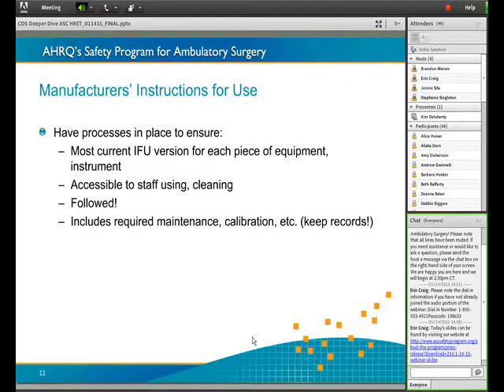So diving down a little bit more on manufacturer's instructions for use, they have processes in place to ensure the most current IFU version for each piece of equipment and instrument is accessible to staff that's using it and cleaning it, and that it's being followed. A lot of this is monitoring and making sure that you're watching the actual process, not just having them take a quiz, but actually going through and taking the rigor to go through each step of the process.